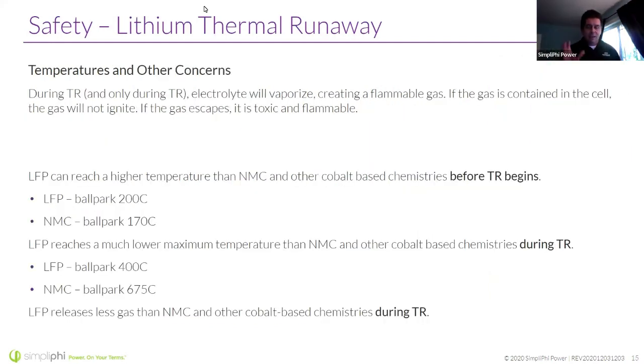When we talk about lithium chemistries, thermal runaway is not universal. It is very different depending on the chemistry. There is a commonality in that in a lithium-ion battery, when thermal runaway occurs, the electrolyte will vaporize. So all the batteries have an electrolyte in them. You get it hot enough, it boils, becomes a gas. They all have a vent, and if that flammable gas vents, it has the potential to catch fire. If that gas is contained in the cell, obviously it won't. But if it does escape, it's not only flammable, it's also toxic.